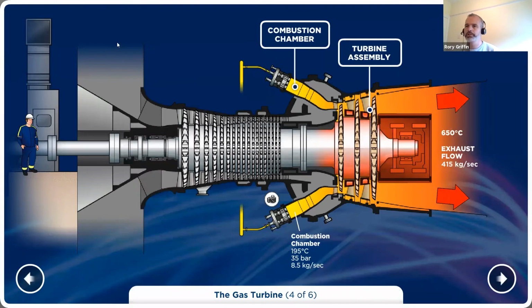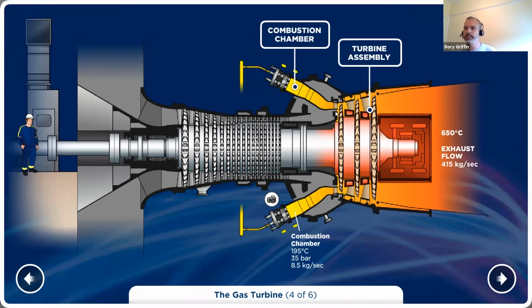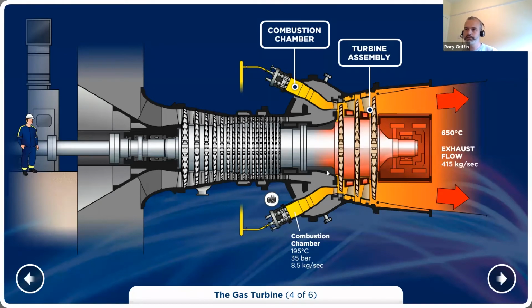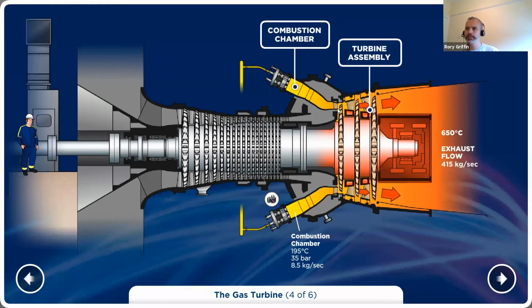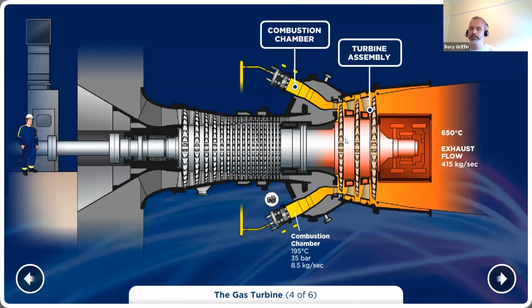So the gas fires down the chamber here, and the first stage of blades will, I suppose, experience the 1400 degrees Celsius, but there is a trick to help the blades a little bit. As part of the air coming in through the compressor, there are actually cooling holes in the blades. So some of the air gets siphoned off through the rotor here, up the top of the blade, and it comes over the top of the surface. So you have 400 degree air sitting on the surface of the blade. So the blade itself doesn't experience the full temperature of the gas, but obviously it's a very hot environment, and they're very, I suppose, exotic metals being used here. The life cycle of the blade is roughly every 24,000 hours, we'll change them out. Or if you're in a starts environment, that would equate to about 900 starts.